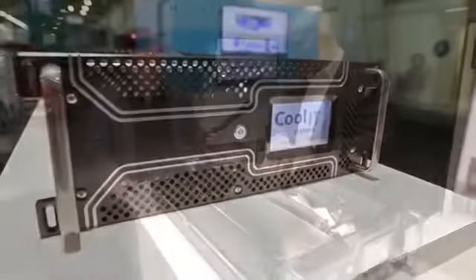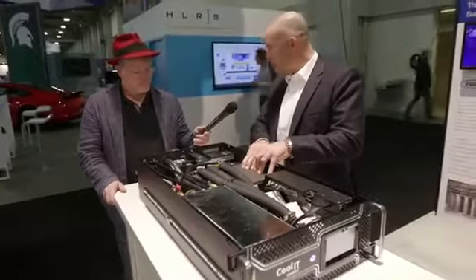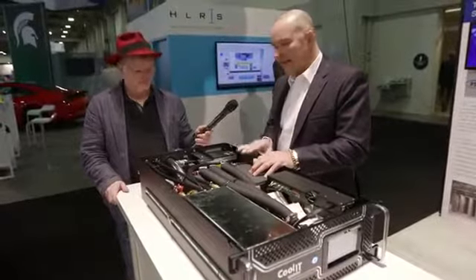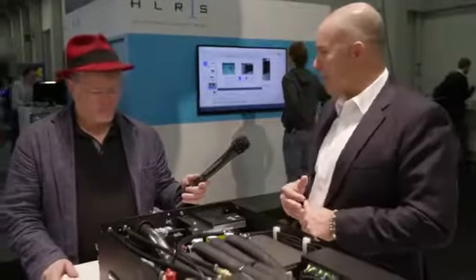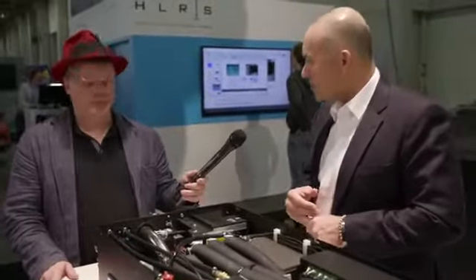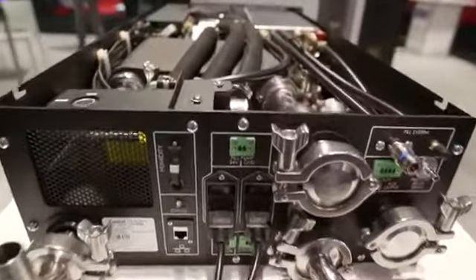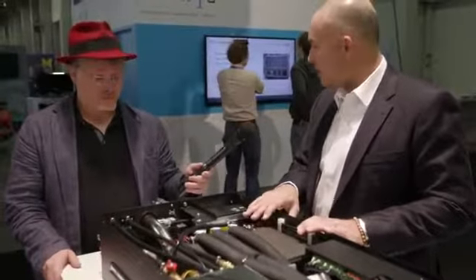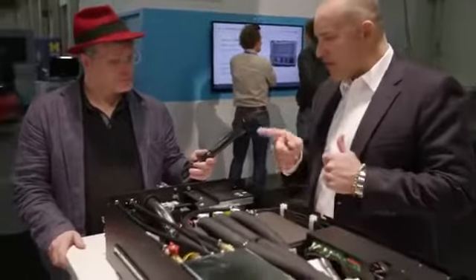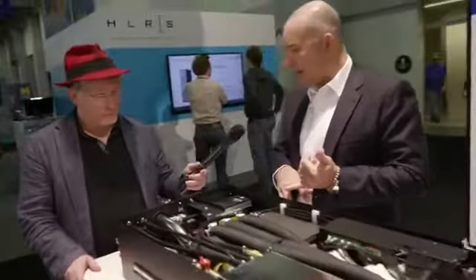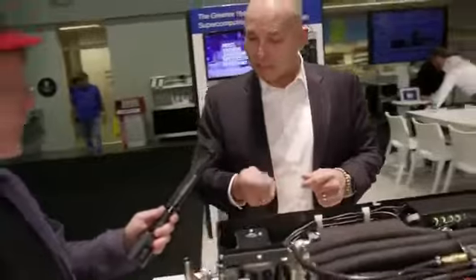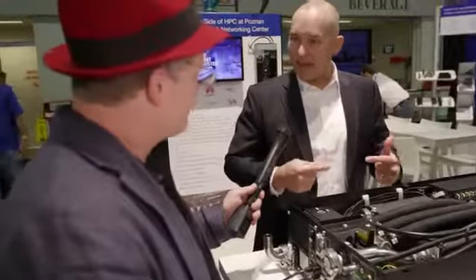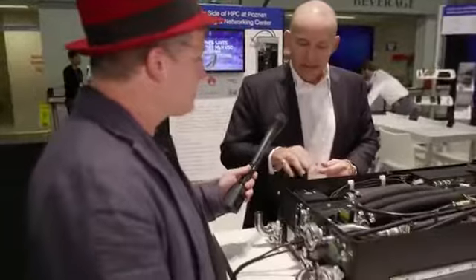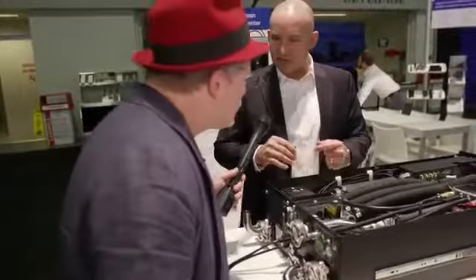And we also have a much increased brazed plate heat exchanger, so it has a much higher capacity, higher flow capability. Instead of 20 liters a minute, we're upwards of 60 liters a minute, so that we're able to push over 120, 130, 140 nodes with one CHX module. It also has flow measurements on the primary, flow on the secondary, pressure and temperature on in and out on primary and secondary. It has a diverting valve instead of a proportionate valve.